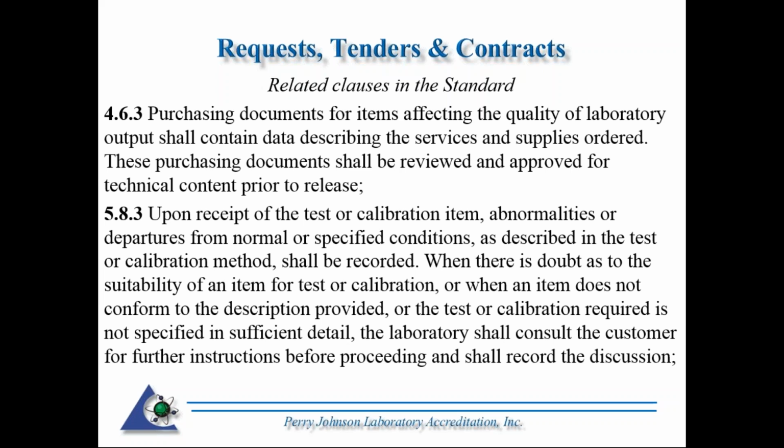For example, if you're a calibration laboratory and you have different levels of calibration, and you have a purchase order that says, and I've seen this on an assessment before, please calibrate, please certify, something like that, that's not enough information. Hence, the lab generating the purchase order, if they were actually under 17025 accreditation, is not fulfilling the requirements of 4.6.3.